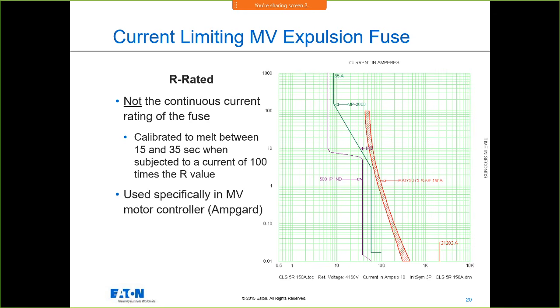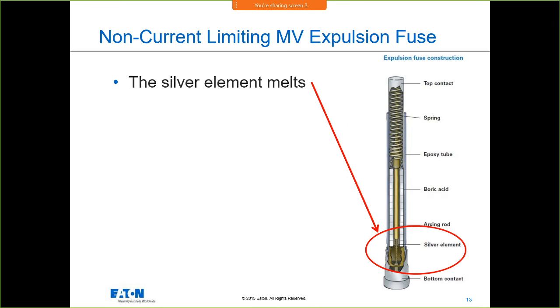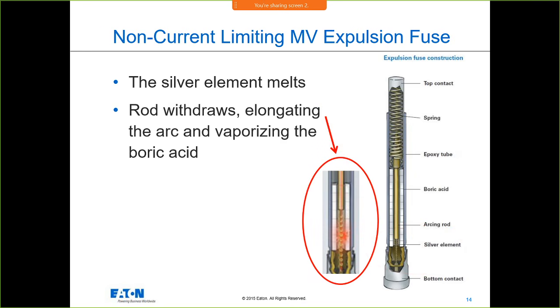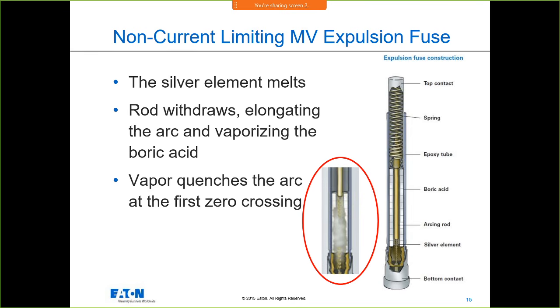I want to re-show the internals of a medium voltage fuse. They wanted me to, and yeah, I did go through that pretty fast. Sorry about that. So there's your internal: you've got a spring, an epoxy tube, boric acid, and your arcing rod. This is your expulsion type fuse. I'll walk through this again because somebody wanted to see it, and I will oblige. That's basically how it works. You can always go back to the YouTube and watch it again. But that's basically how that puppy is working.